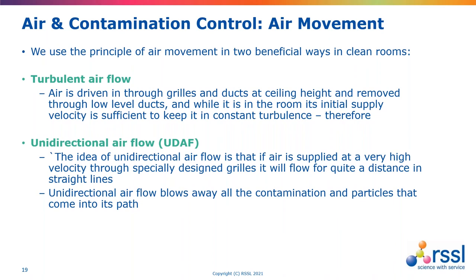With grade A areas, we have unidirectional flow — what in the old days was called laminar airflow. If air is supplied at very high velocity, driven through specially designed grills, it will flow for a reasonable distance at a desired velocity in a single direction. The idea is that unidirectional airflow blows away contamination and particles that come into its path, creating a curtain of clean air sweeping particles and microorganisms away from vials. This activity should be confirmed periodically by airflow visualization or smoke study tests, which are recorded to show the degree of air protection in place.